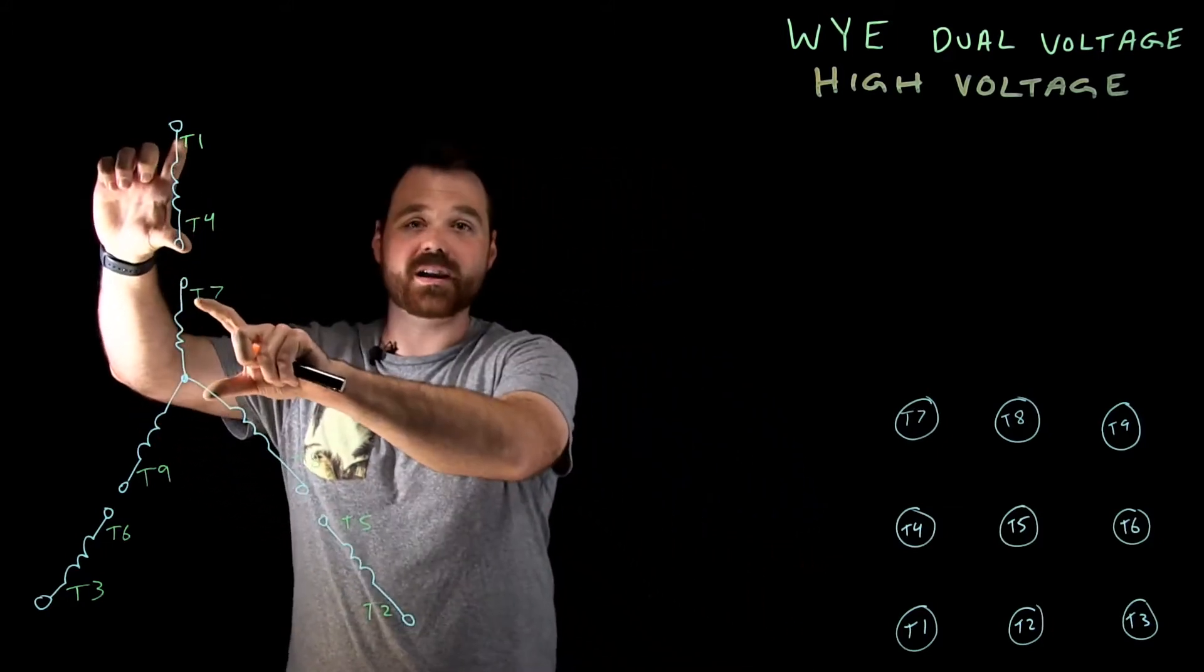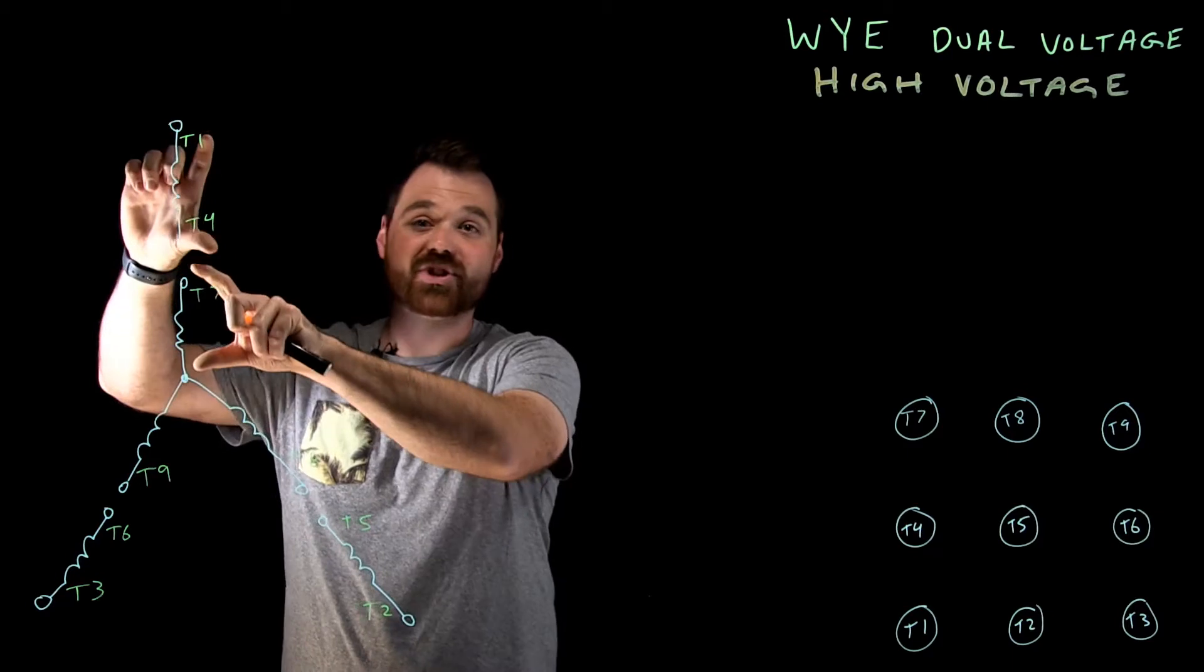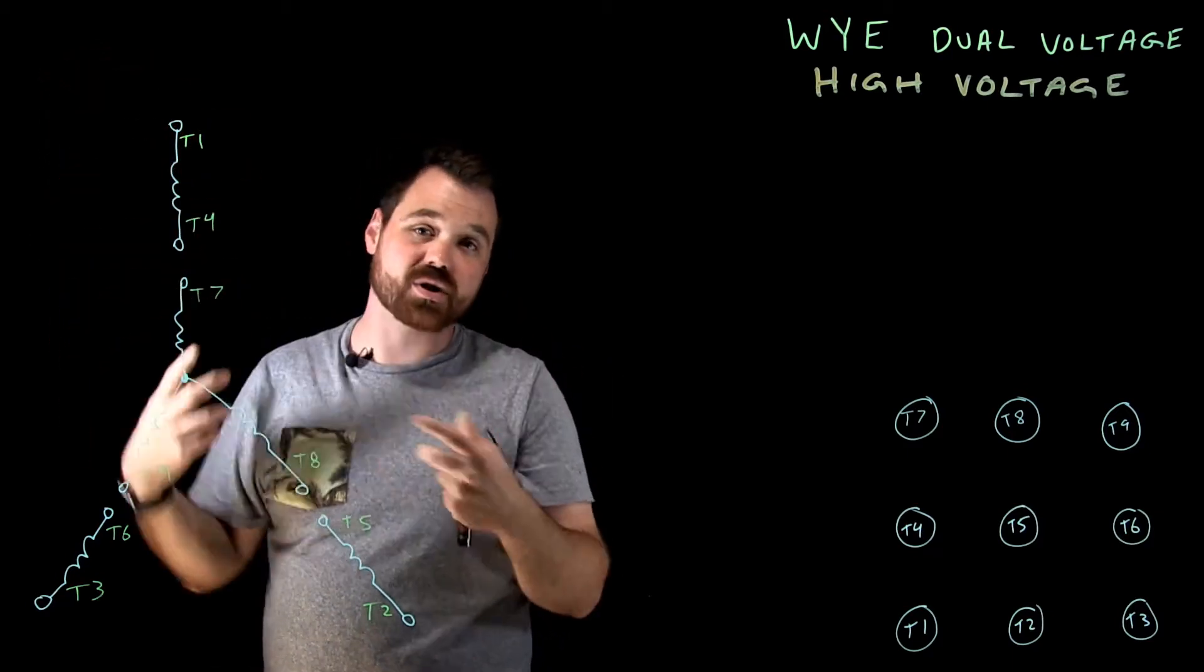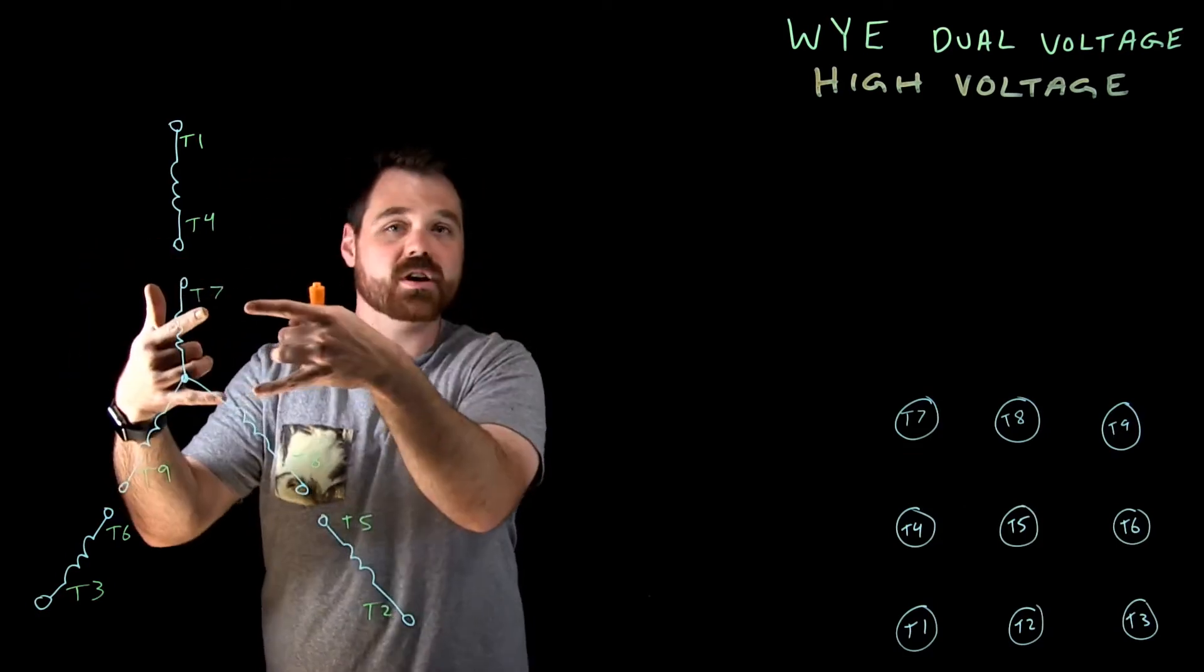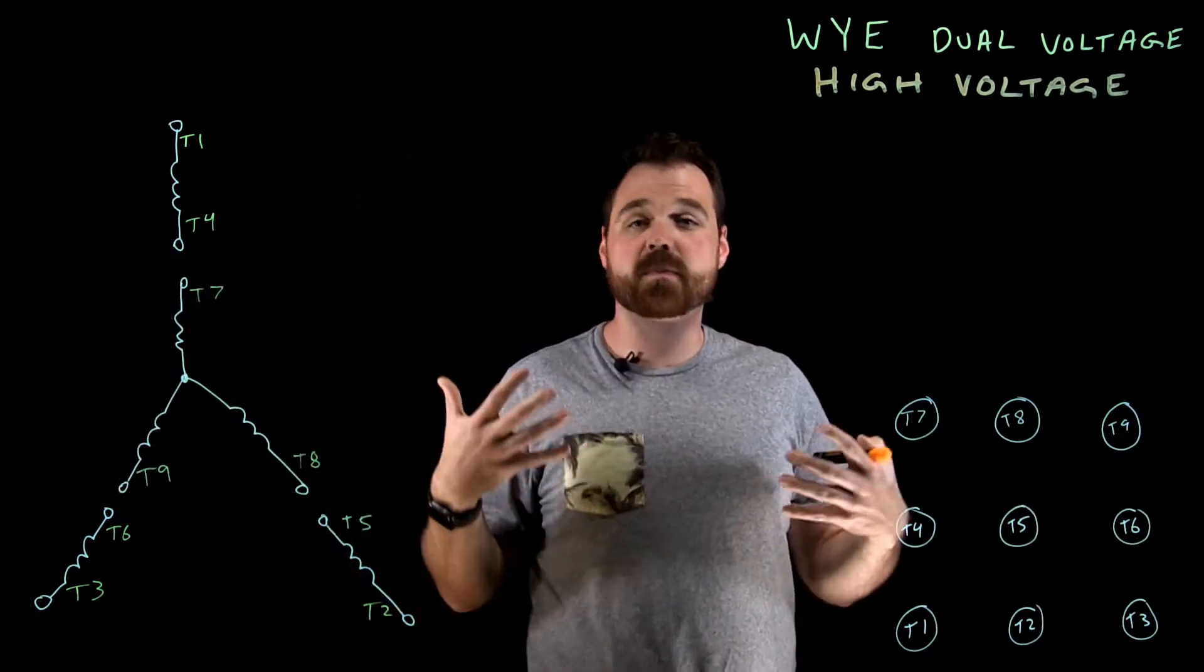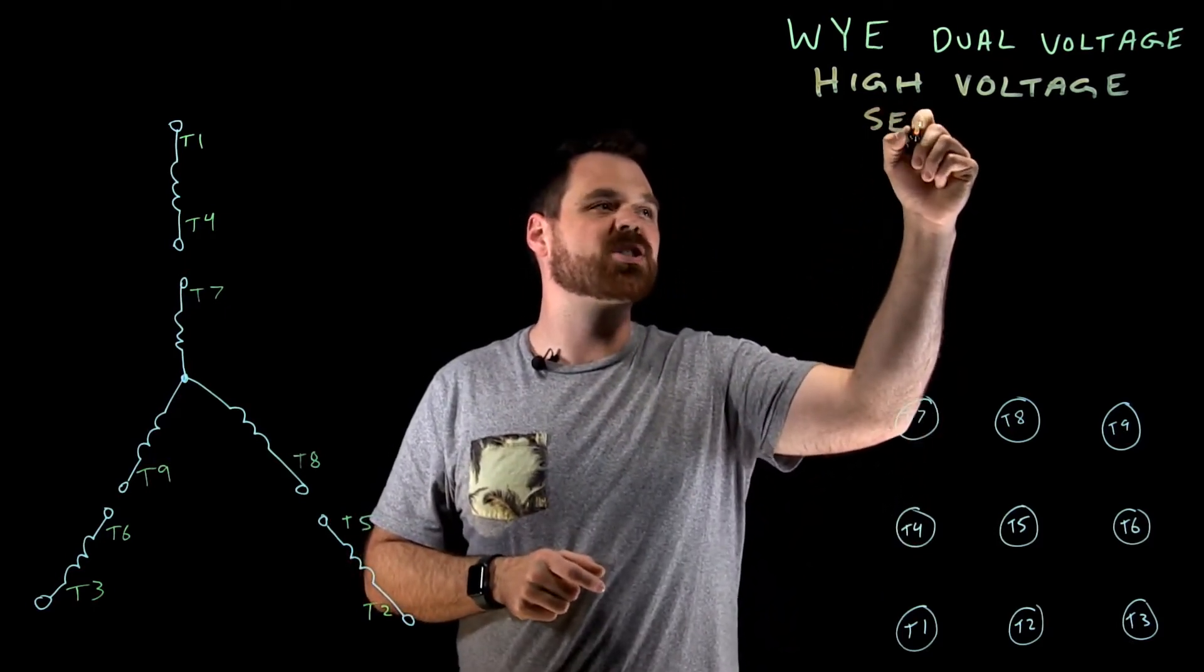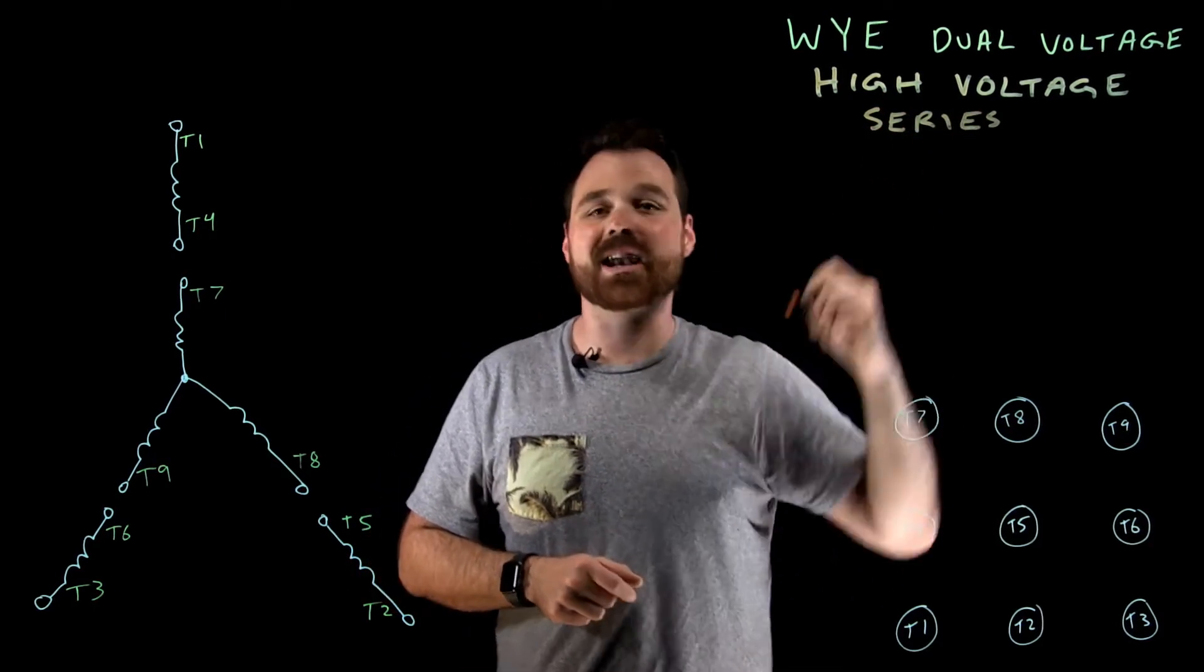If I put these two windings, which are both rated for 240 in series, then I can apply 480 volts across it. If I put them in parallel with each other, that's going to only allow me to put the lower voltage. So in this case, we're a high voltage connection. So we are talking about a series connection.